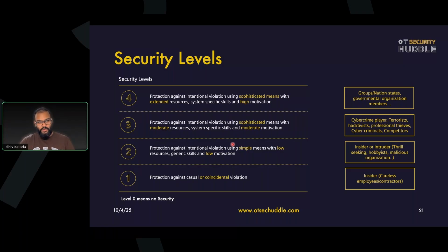Security level 4 says that all the assets in your ICS would require multi-factor authentication. Implementing a technology that allows two-factor authentication would be very costly, and it's not necessarily required everywhere. The same essential function requirement also applies here. Your PLC, which is controlling your safety system, is a very critical asset, and it might require immediate access during the time of an incident. So you would never want to put multi-factor authentication or a complex password there. All of these security requirements need to be assessed through a risk assessment procedure and then implemented accordingly.